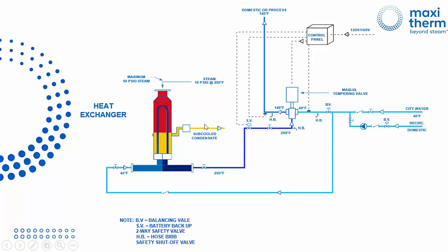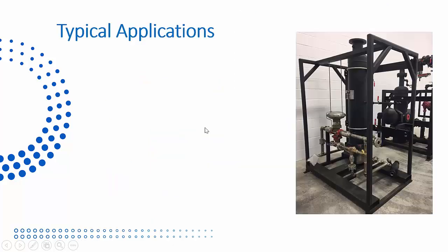So we make minimum 5% energy savings over the others. And we can use, it says 50, I would suggest 40 PSI through the heat exchanger. So you will need just one pressure regulator, no one-third, two-third, because we don't modulate on steam. No steam safety relief valve, because we're going to stamp the whole skid as a high-pressure vessel. And again, if the condensate back pressure is lower than your steam pressure, we don't need a condensate pump.